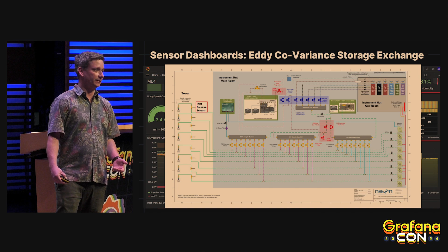So this panel below here shows the concentration of carbon dioxide from the air measured across two different gas analyzers on site. And zooming up on these two panels gives you some idea of how we cycle sampling levels on the tower. Also what it looks like when one of the gas analyzers undergoes a daily calibration, receiving low, medium, and high span gases.